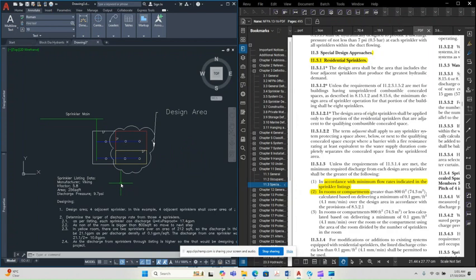Once the design area is defined, the next step is to make sure that there is no combustible ceiling space around, as defined in clauses 8.15.1.2 and 8.15.6. And these ceilings above our rooms are not combustible ceilings, and those ceiling areas do not need protection from fire. So the next step is to make sure what kind of sprinklers you are using for your particular project.